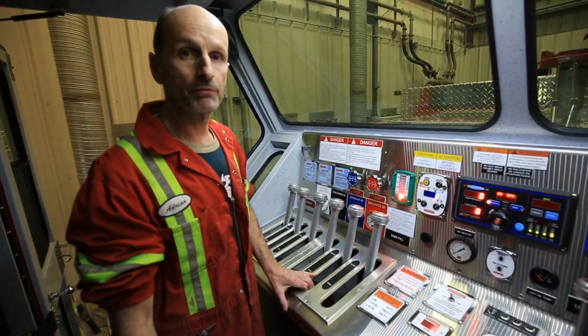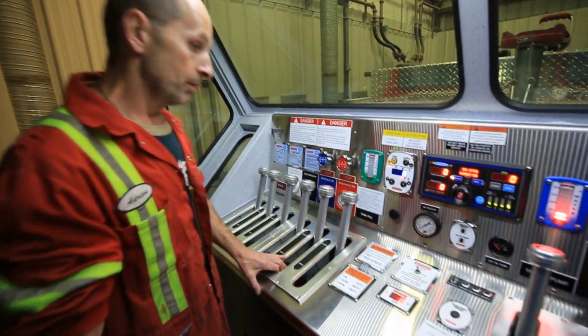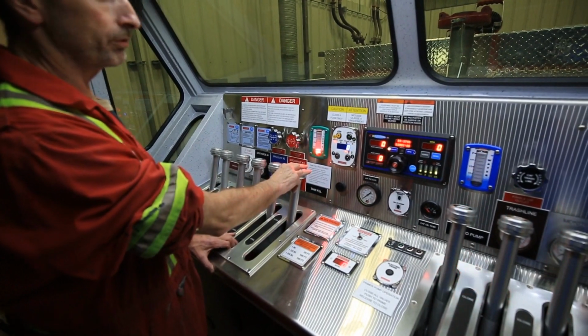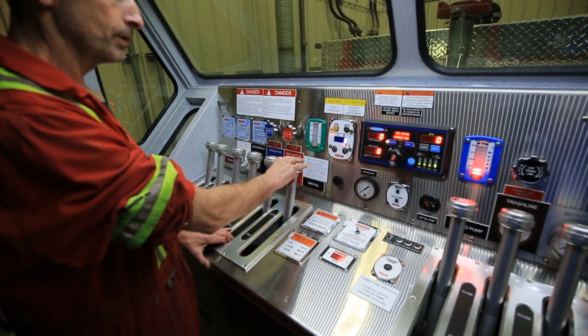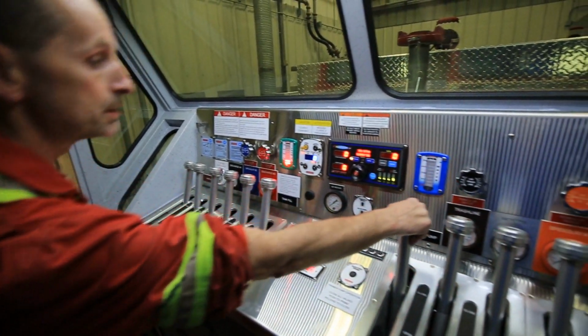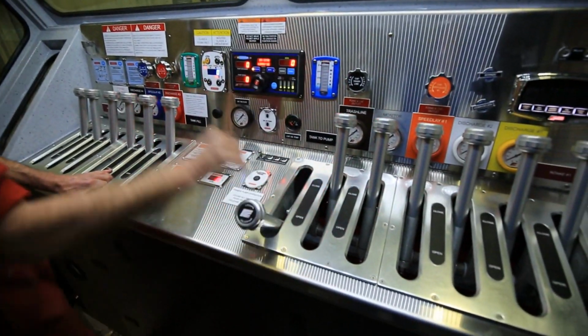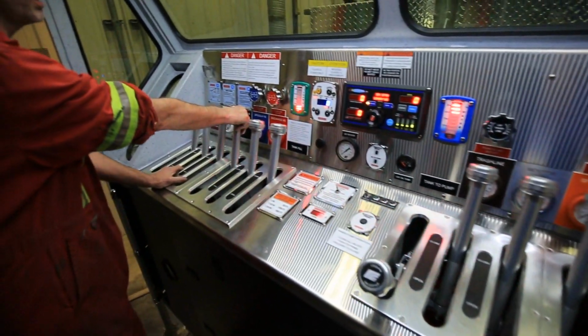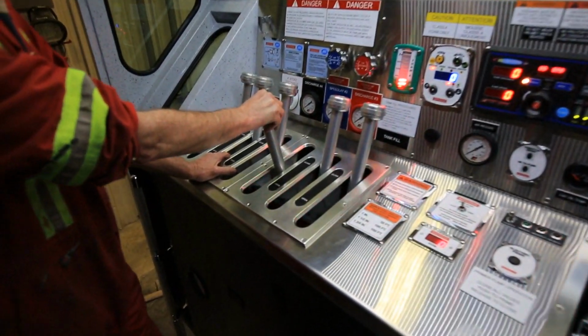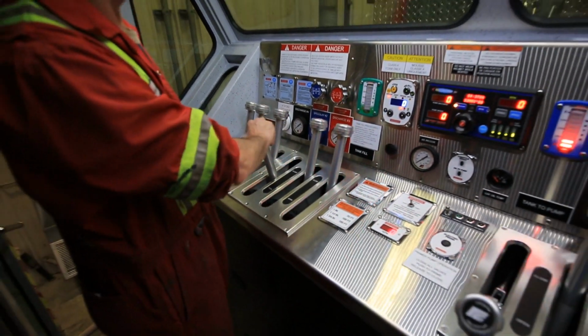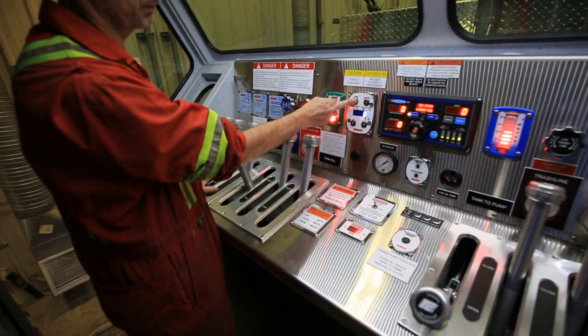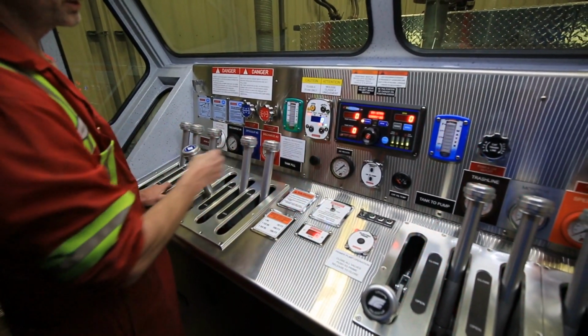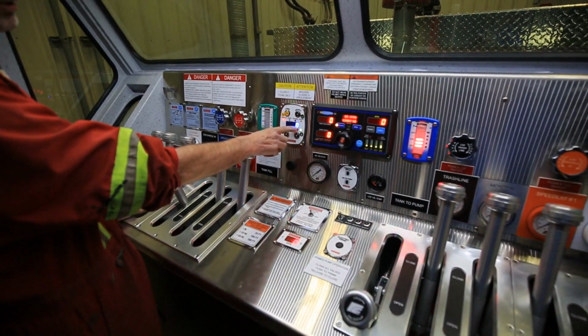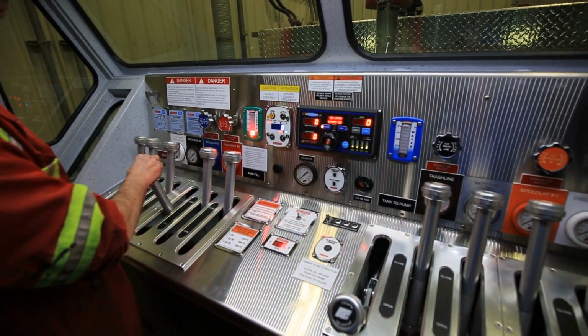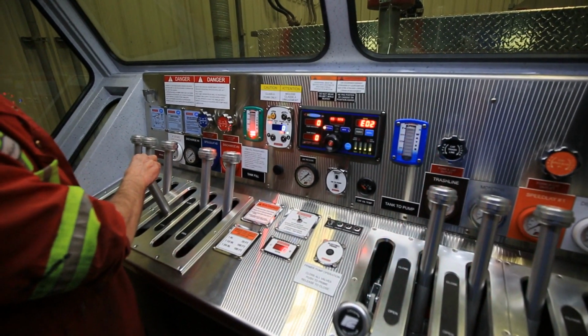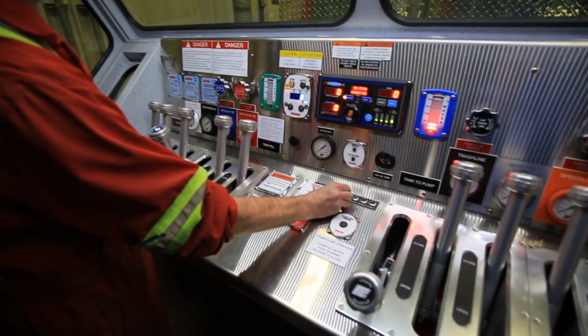The actual operation of the CAF system on the fire truck: first of all, establish water flow from your fire pump. So either draft or open your tank to pump. And if you're fighting a fire, open the discharge. Once you've got water flowing, the foam system can be engaged. Green light to say the foam system is running. The digital display will show the amount of water flowing.